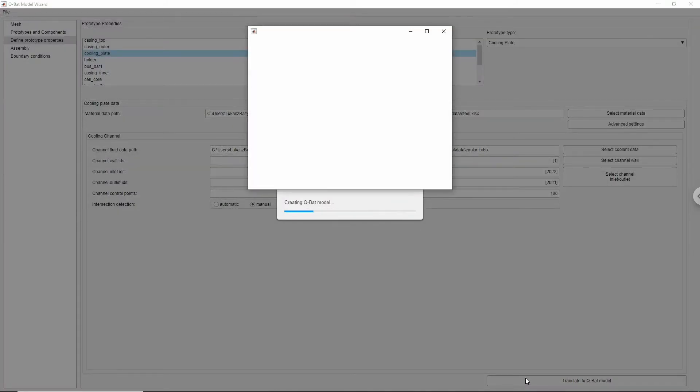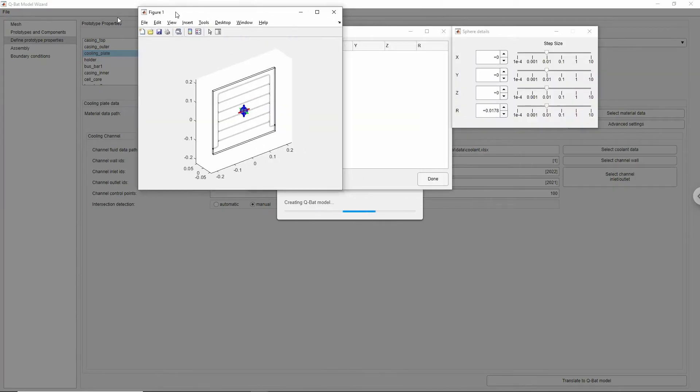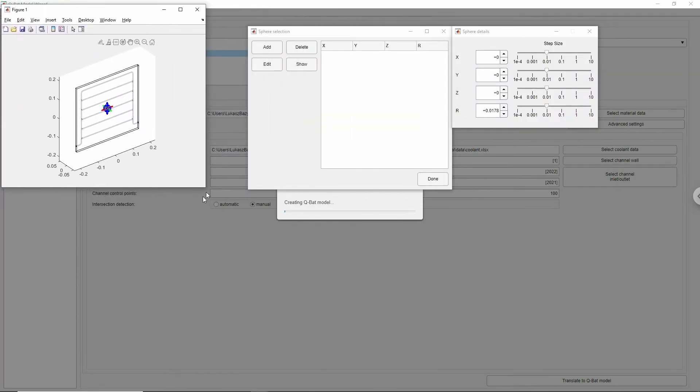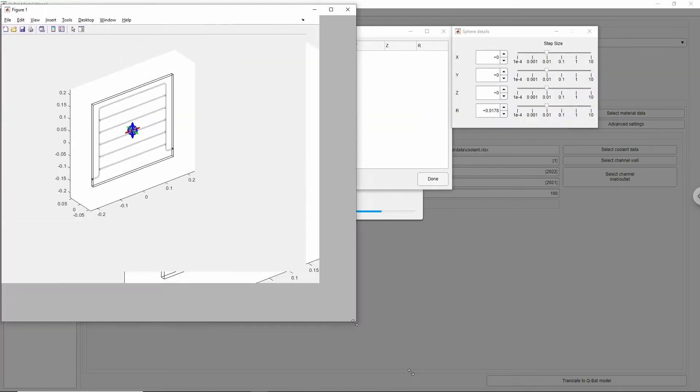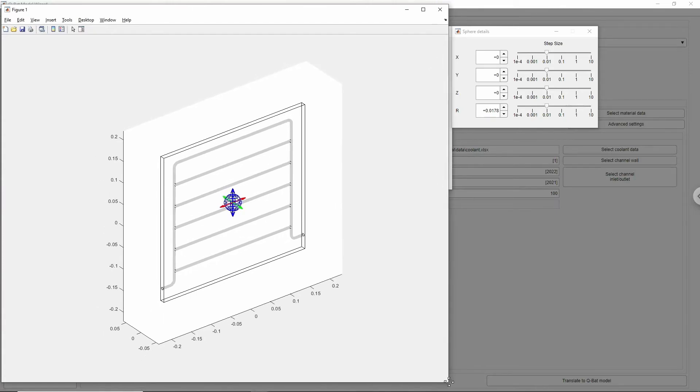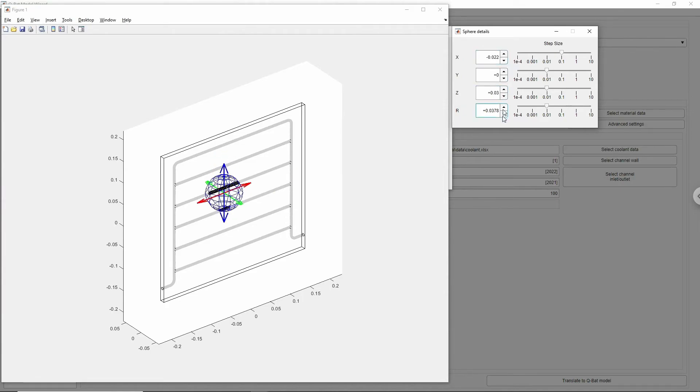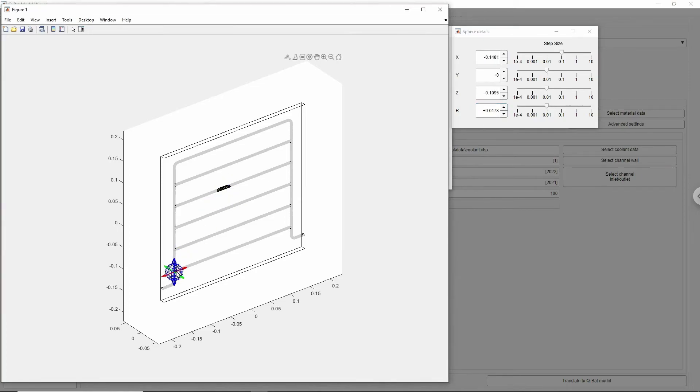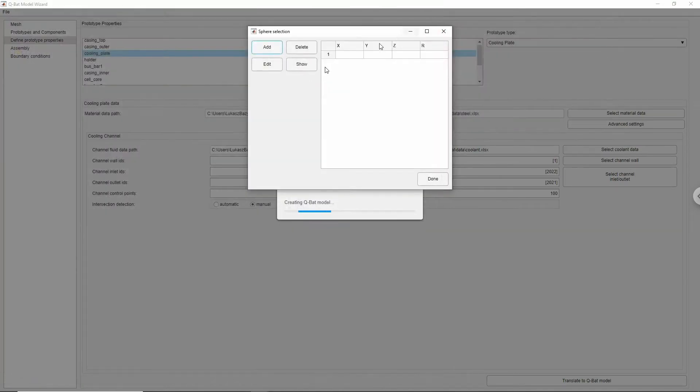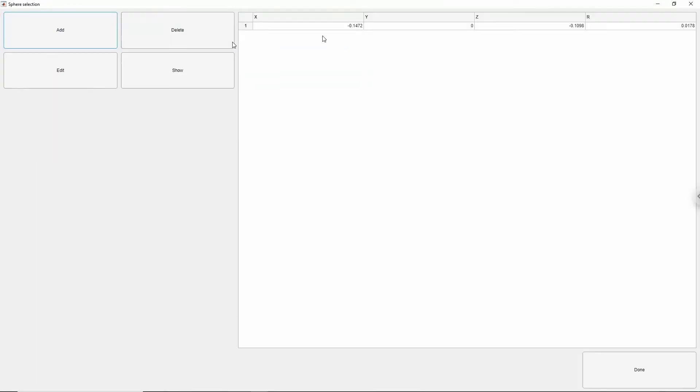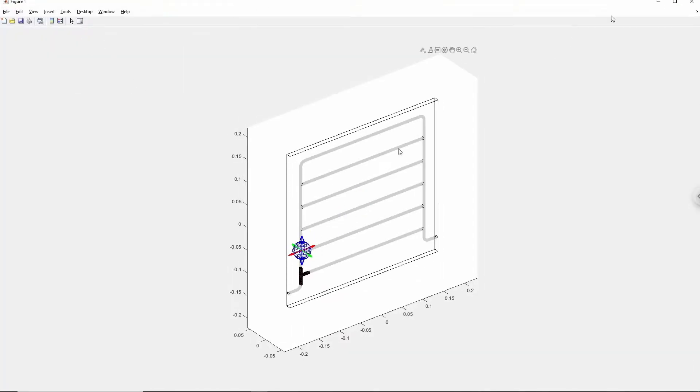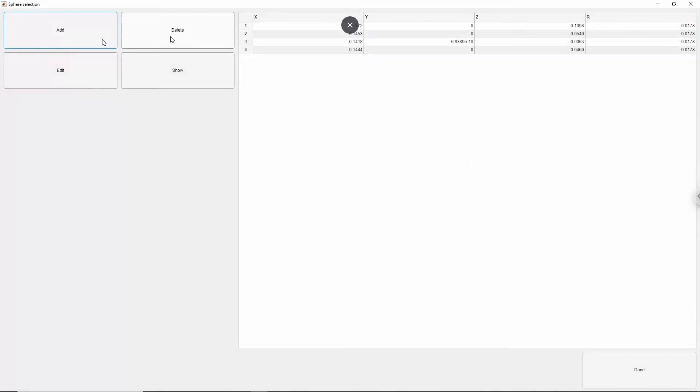At this point, the computational model is generated based on the user input. This is also the moment when you need to manually add cooling pipe intersections. Click Add and a new window will pop up showing your cooling pipe geometry and a ball with coordinate system directions. To detect the intersection, you need to place the ball in the way that it is completely covering an intersection. You can move the ball using navigation buttons where you can adjust step size by the slider or you can type in the desired coordinates directly into the box. You can also click the ball and move it using the mouse. Once you have moved the ball to the correct position, exit the window to confirm. You need to repeat this action for each intersection and end the whole operation by clicking Done.